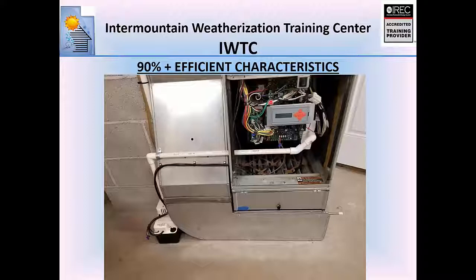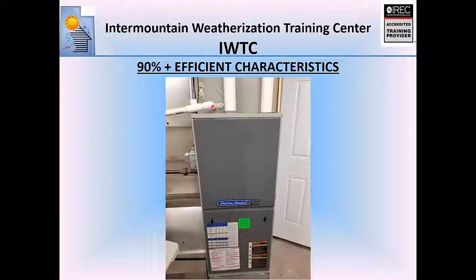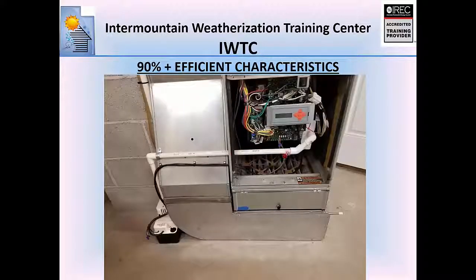The other thing is anything over 90% is going to have some kind of condensate drain that comes directly out of the furnace. So here I've just pulled the door off the furnace to verify. Yep, I can see I've got a condensate trap in here with some plumbing that runs over to a pump. Now don't get that confused with this drain up here. You can have a furnace that's not a 90% and still have a condensate drain coming off the coil. This is for the air conditioning side. If it's 90%, you're going to have a condensate drain coming directly from inside the furnace somewhere and then going out to some sort of drain. So another dead giveaway of what kind of efficiency you're dealing with.